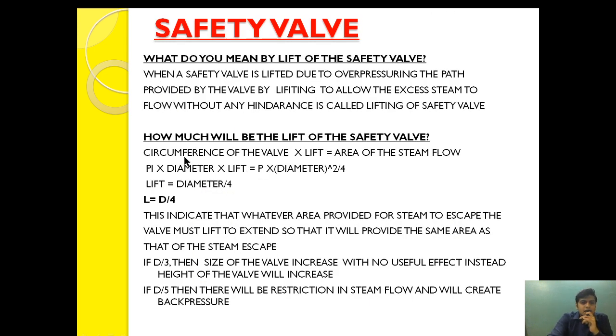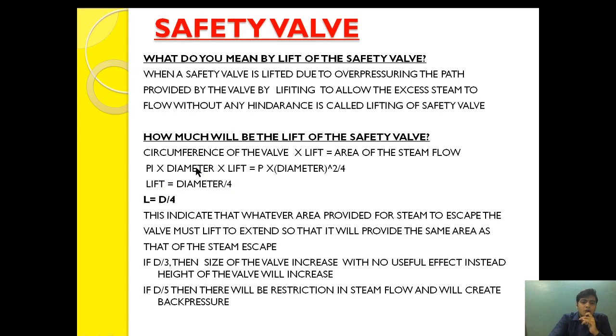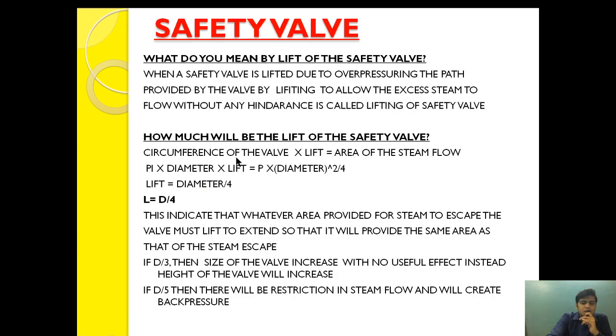The first formula is: circumference of the valve multiplied by the lift equals the area of the steam flow. The valve sits on the circumference of the flow area, and lift is denoted as L. Circumference of the valve multiplied by lift equals the area of the steam flow. Now substituting: circumference of the valve is π × diameter (i.e., 2πr), so 2πr × L equals the steam flow area.